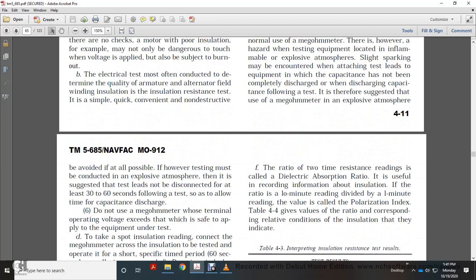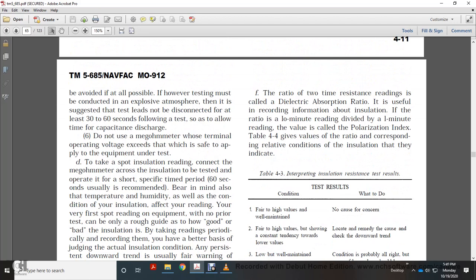Use of the megohmmeter in an explosive atmosphere is not suggested. Avoid it wherever possible. However, if testing must be conducted in an explosive atmosphere, the test leads must be kept connected for at least 30 to 60 seconds following the test, to allow time for the capacitance to discharge. Do not use a megohmmeter with a terminal operating voltage exceeding the rating for the safety of the equipment under test.